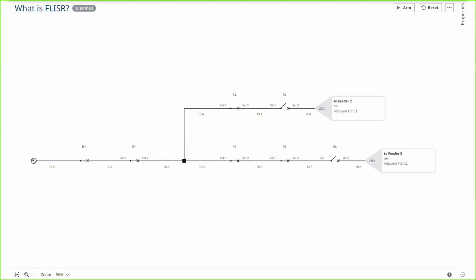So here you have a distribution feeder, lots of reclosers, 6 of them, with a line tap, and a breaker on the left. The high side of the breaker is to the left side of the breaker. So there's a source of energy flowing from left to right in this picture. What we're going to do here is just demonstrate what this feeder would experience if FLISR did not exist.